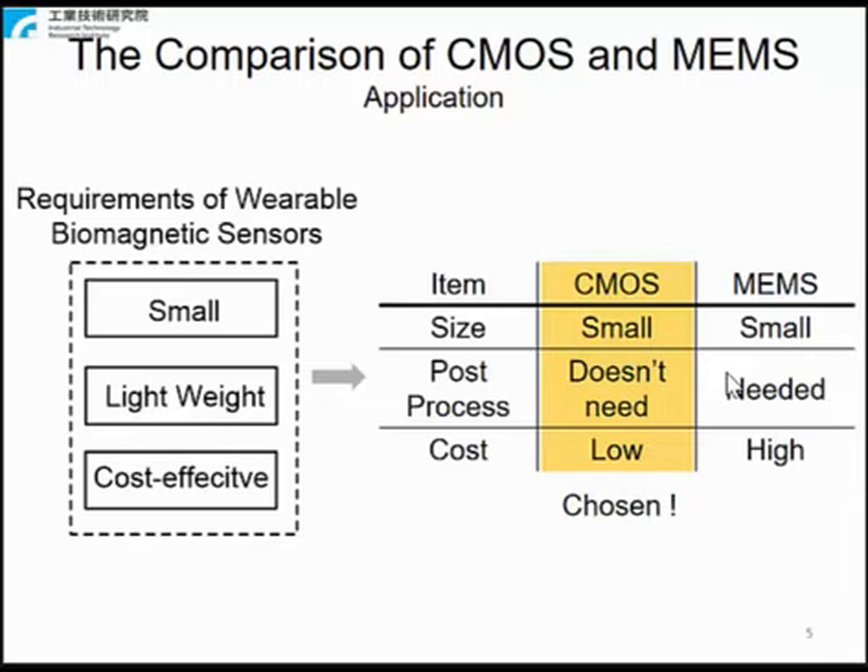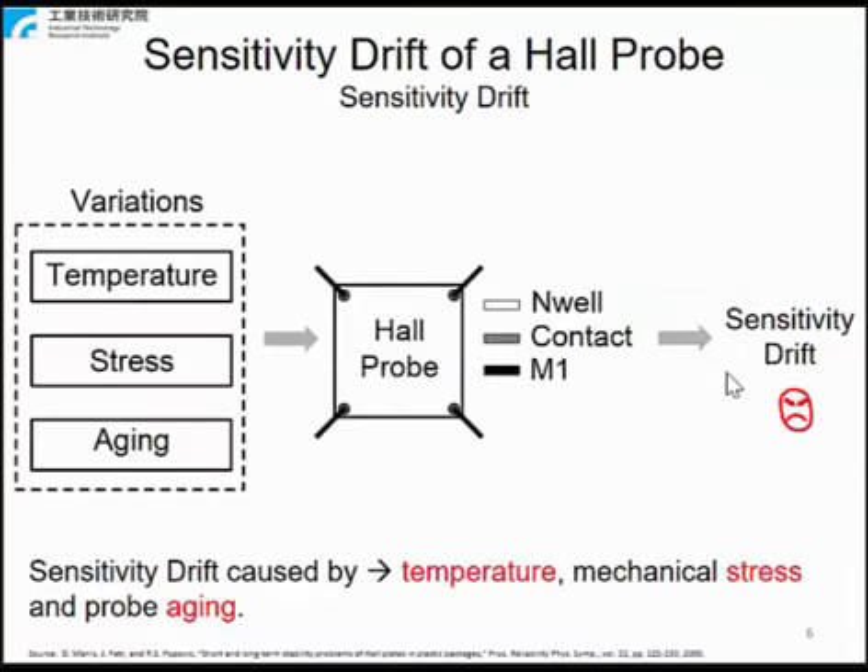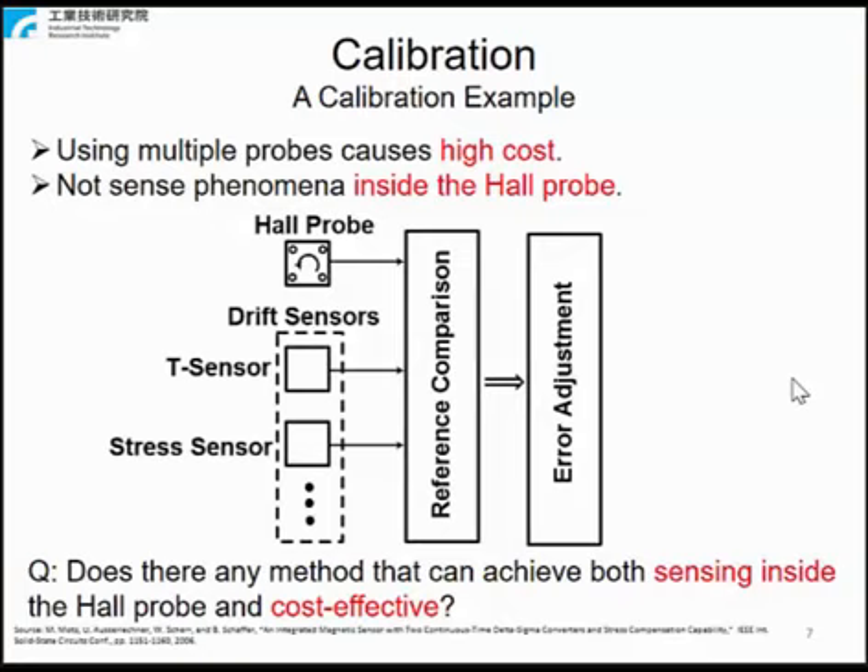To detect magnetic fields, a Hall probe is integrated in the circuit. However, the sensitivity variation of an uncalibrated Hall probe is poor. A Hall probe's accuracy varies with temperature, mechanical stress, and probe aging that causes its sensitivity drift. To reduce sensitivity drift in a Hall probe, a calibration mechanism should be applied into the Hall sensor.